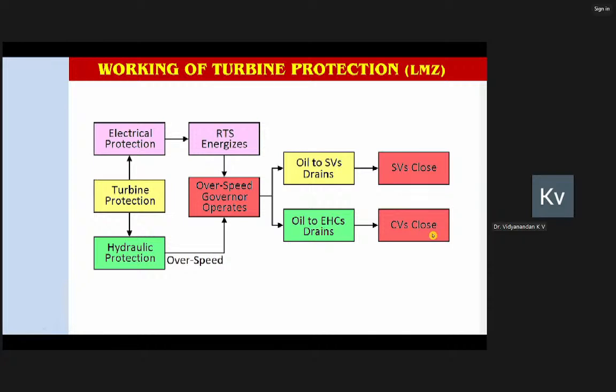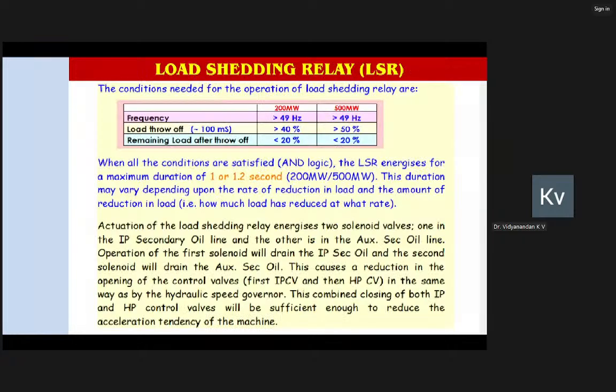There are certain additional special devices also provided over and above the turbine protection, because turbine protection is a classical design meant for taking care of normal abnormalities like pressure going high, temperature going high, expansion, vibration, etc. Over and above that, from the system point of view, whenever any sudden reduction in the load occurs, the normal response of the governor may not be adequate to support the power grid under that condition. So there are certain special devices. One such important device is the so-called load shedding relay. It will come into action only under certain conditions because it is not an ordinary protective device. For the operation of this device, the typical logic is that your machine frequency or the power grid frequency must be more than a certain preset value. Earlier, it was 51 hertz. Subsequently, they have reduced the set value to 49 hertz.